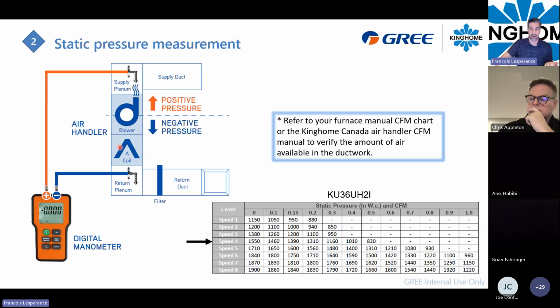So only the coil will be in the supply, versus now, in this picture, it's in the return here. But you will have the same kind of measurement to take. In that example, it's an air handler. You will just make a little hole in the return side of the duct after the filter, and in the supply duct right here. And you can take the differential between those two. That will give you a number in inches of water column.